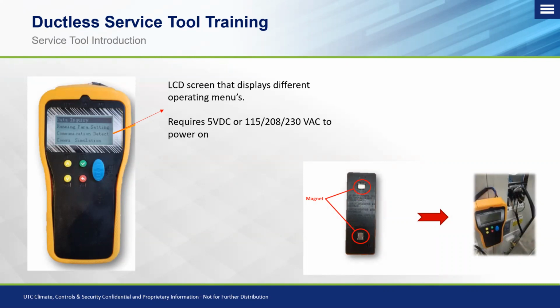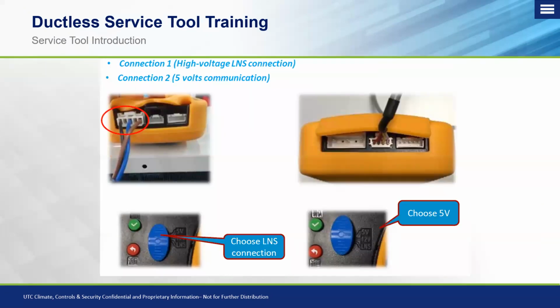The biggest thing with this is going to be when you're plugging in for power. I talked about the 2 different connections on there. You're going to get 2 different wiring harnesses. Connection 1 is going to be for your high voltage, or your L, N, and S, or L1, L2, and S connection. And that, of course, is going to wire on the bus bar of either the outdoor unit or the indoor unit, depending on what information you're trying to gather.